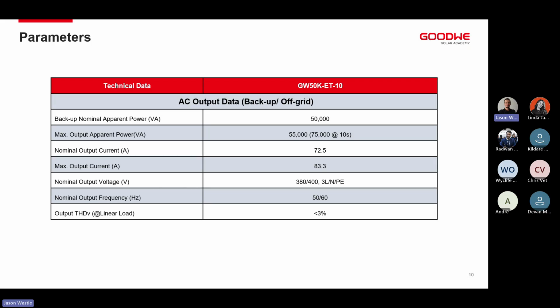Obviously, there are certain conditions where this isn't the case, when we've got bigger inductive load startups and that kind of thing, which we obviously are seeing now in the C&I space. And we're seeing that because of the amount of factories that are not necessarily putting in hybrid systems for full-on backup application, but rather for peak shaving and time of use tariff changes and savings in that space. How can we get around the 75 kilowatt overload timing and that kind of thing?